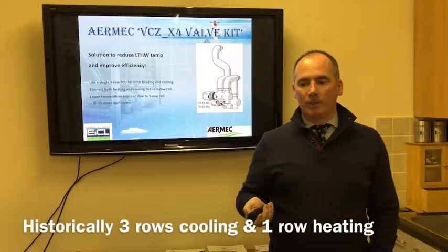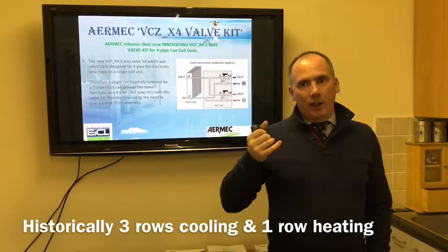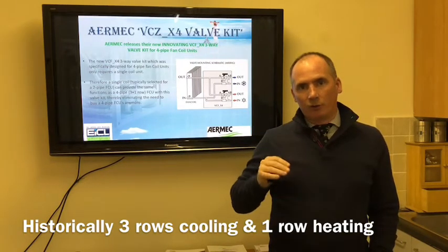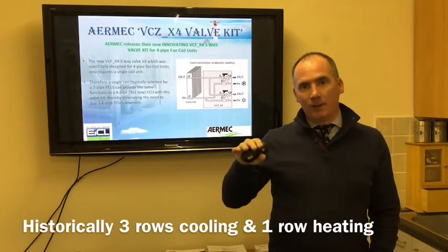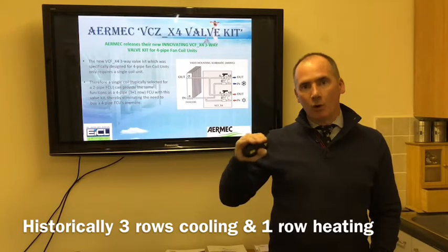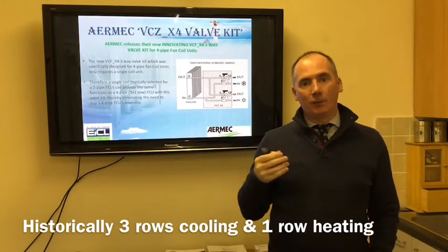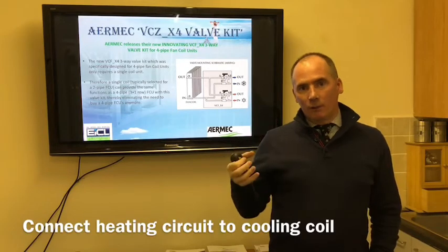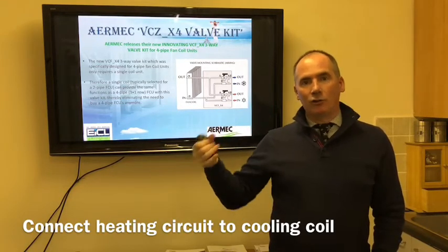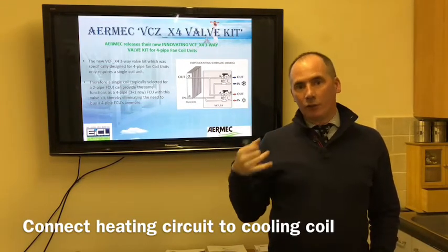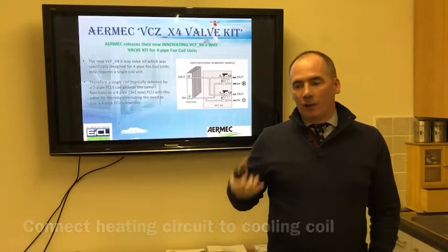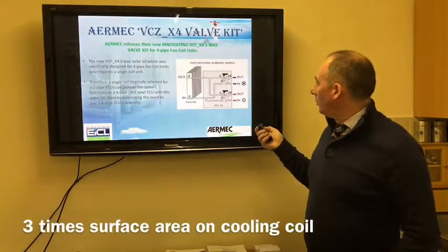Why would you want to do this? Well, on fan coil units you will have 3 rows of copper tubes, aluminium fins for your cooling, and you have 1 row of copper tubes, aluminium fins for your heating. So imagine if you can connect your heating to your cooling coil, you have 3 times the surface area. So you can see here how this works.